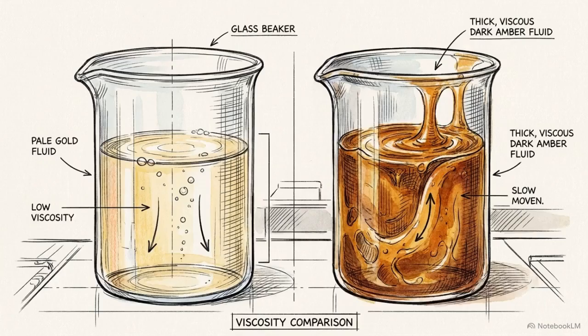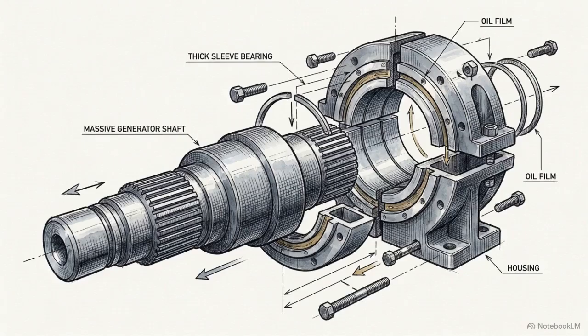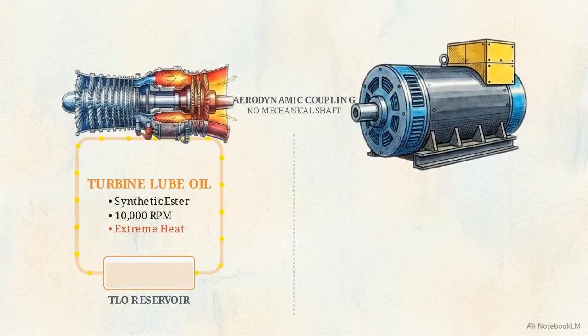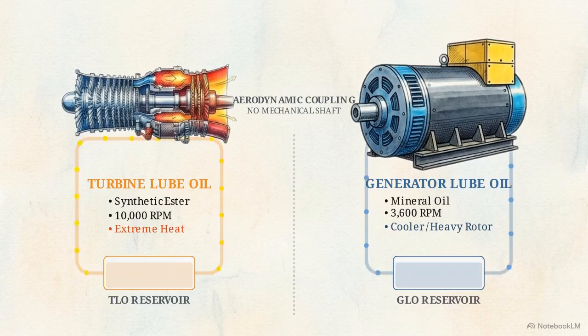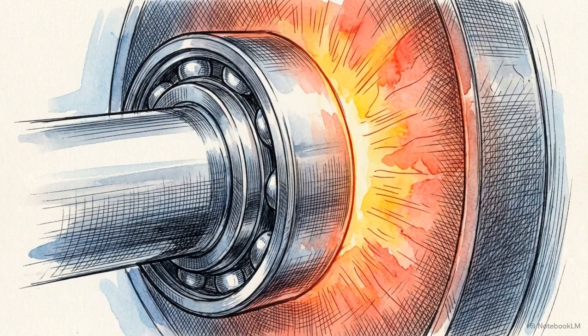The extremes of this machine require 2 entirely separate lubrication circuits. A single oil type cannot satisfy the heat of the turbine and the weight of the generator simultaneously. The gold path represents the turbine lube oil, a high-performance synthetic ester designed for 10,000 RPM and extreme heat. The blue path is the generator lube oil, a standard mineral oil used for the slower, cooler sleeve bearings of the generator. Engineers must keep the synthetic oil contained within a bearing housing that sits inches away from a 1,000-degree gas path.